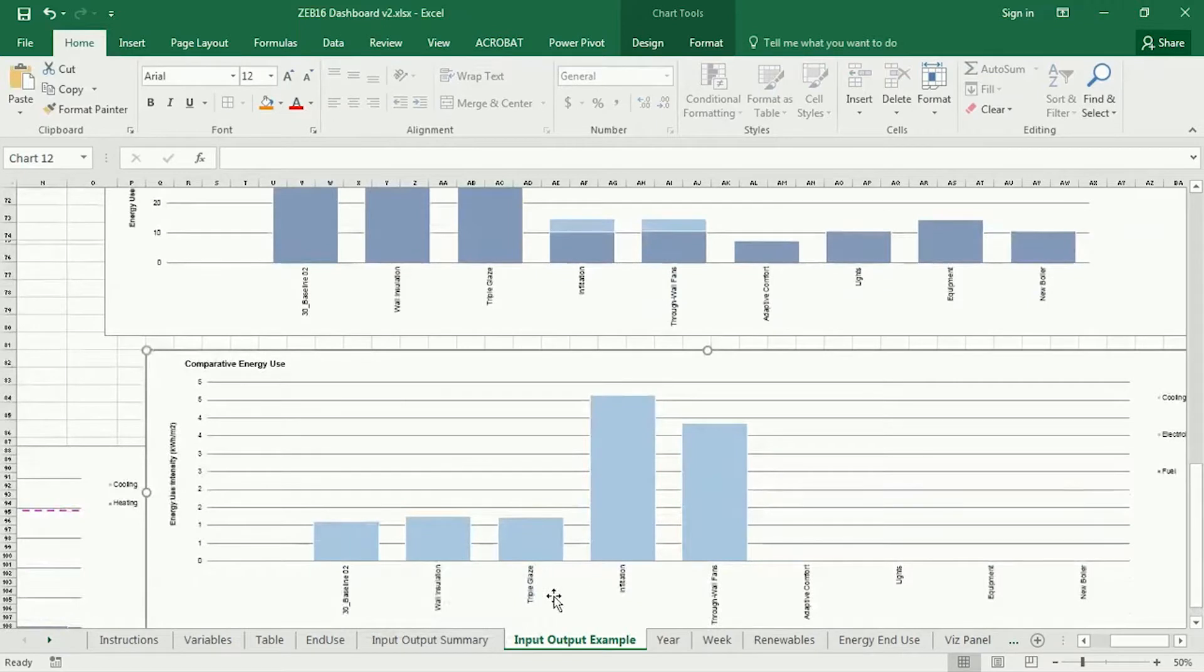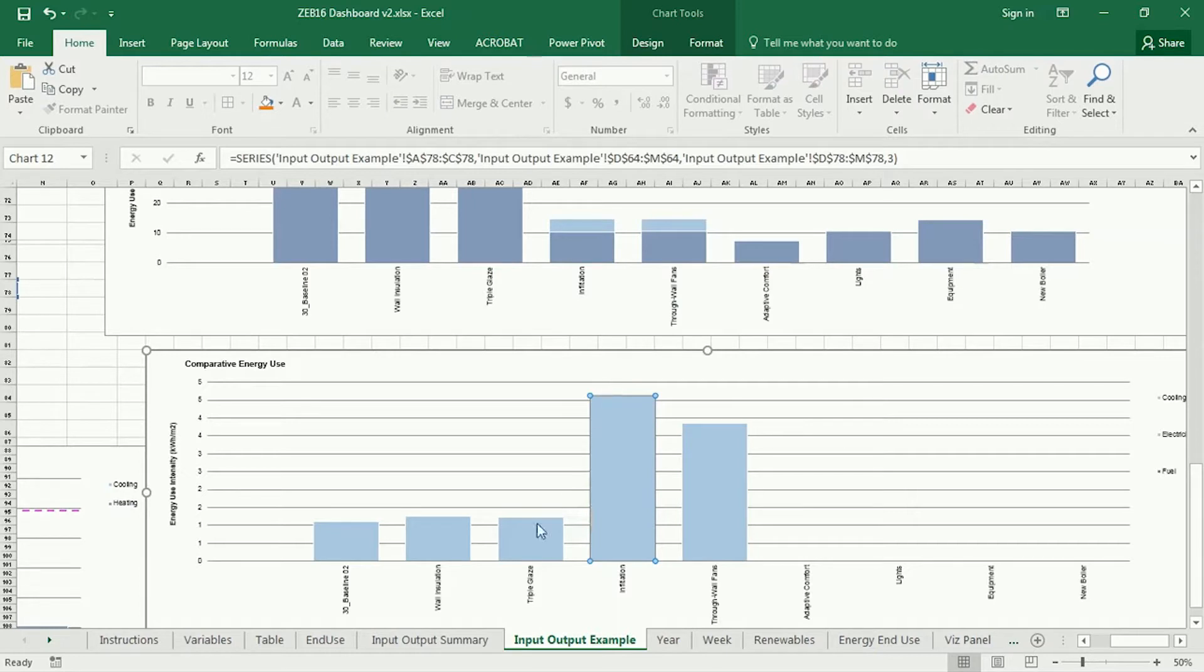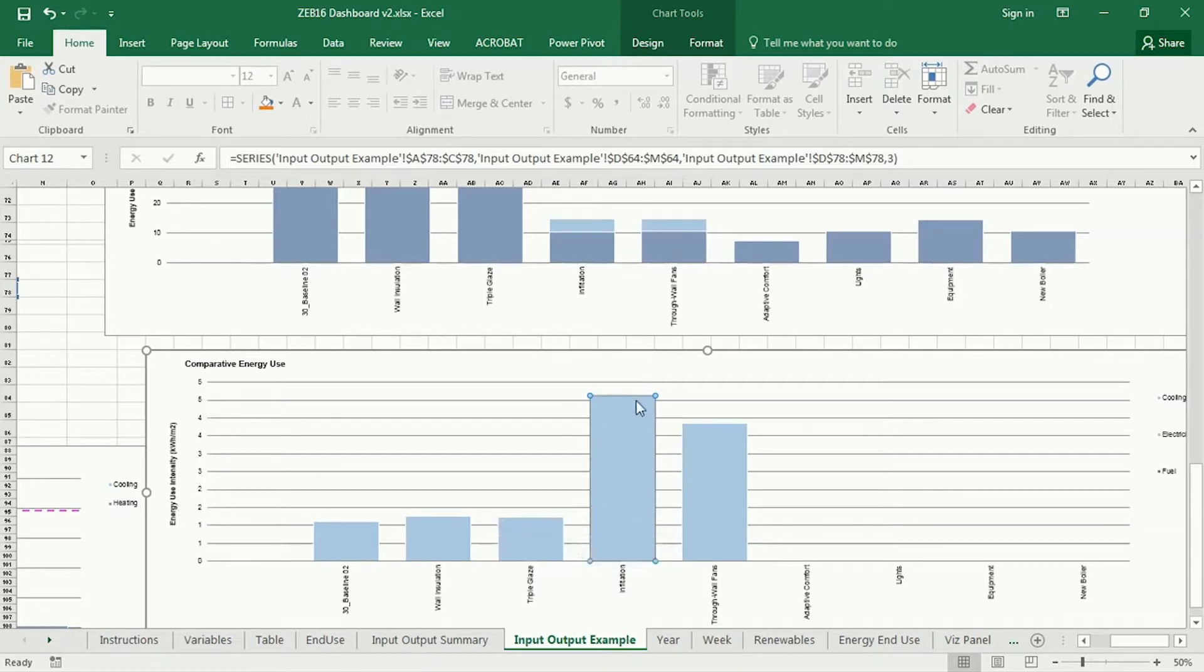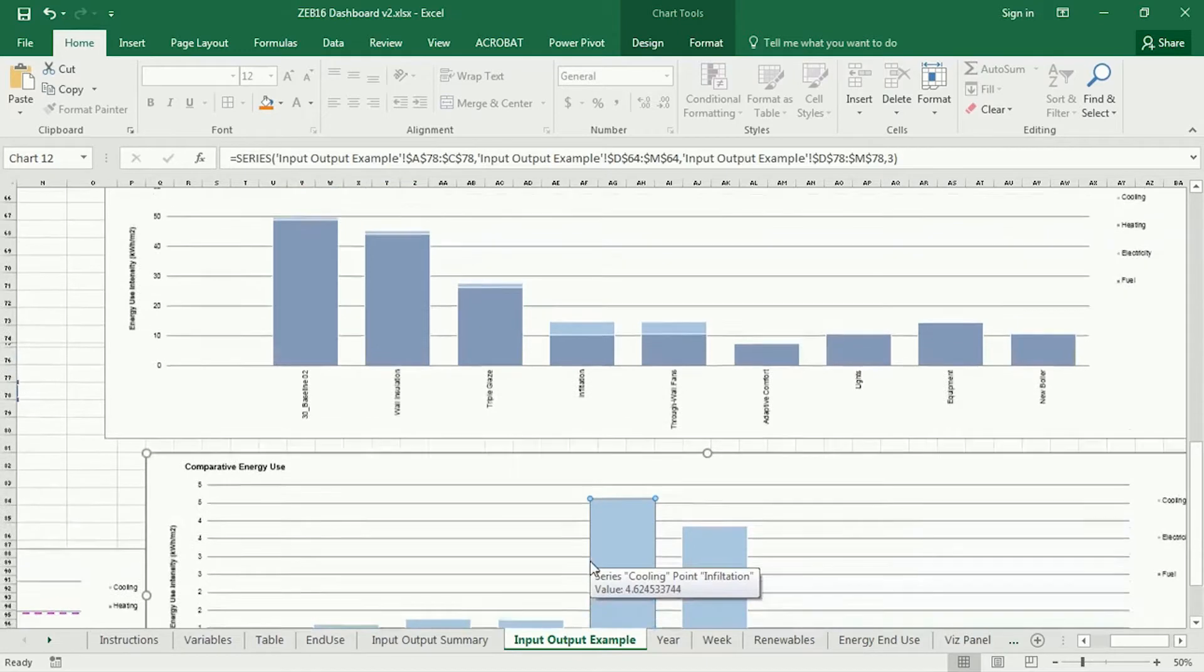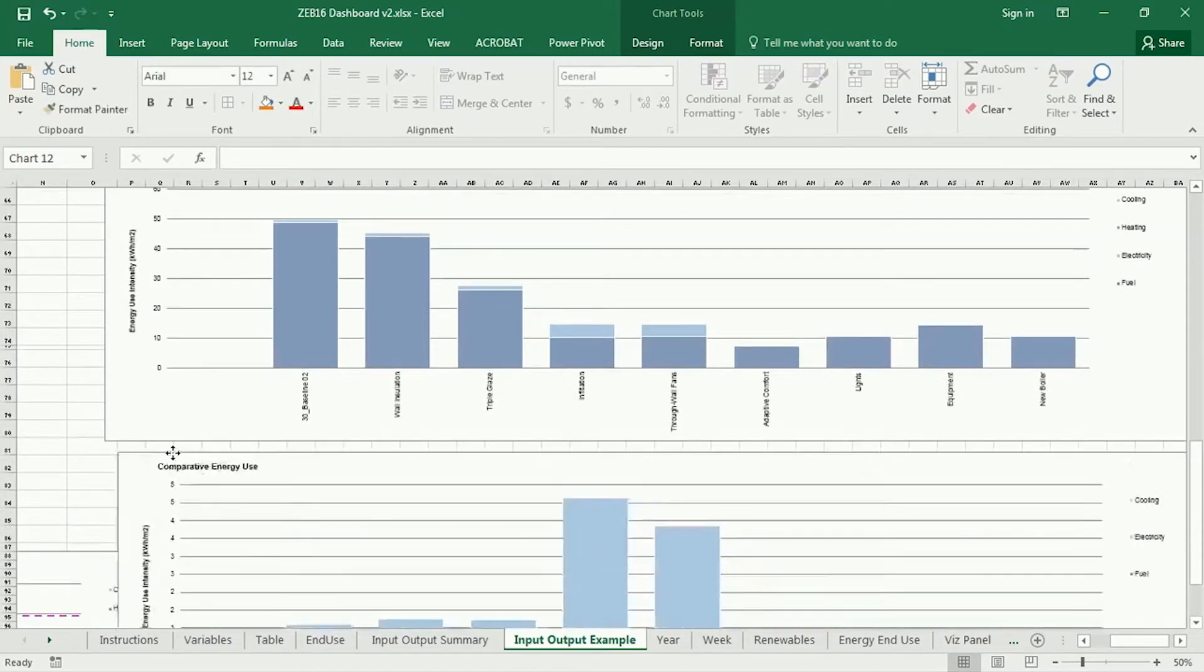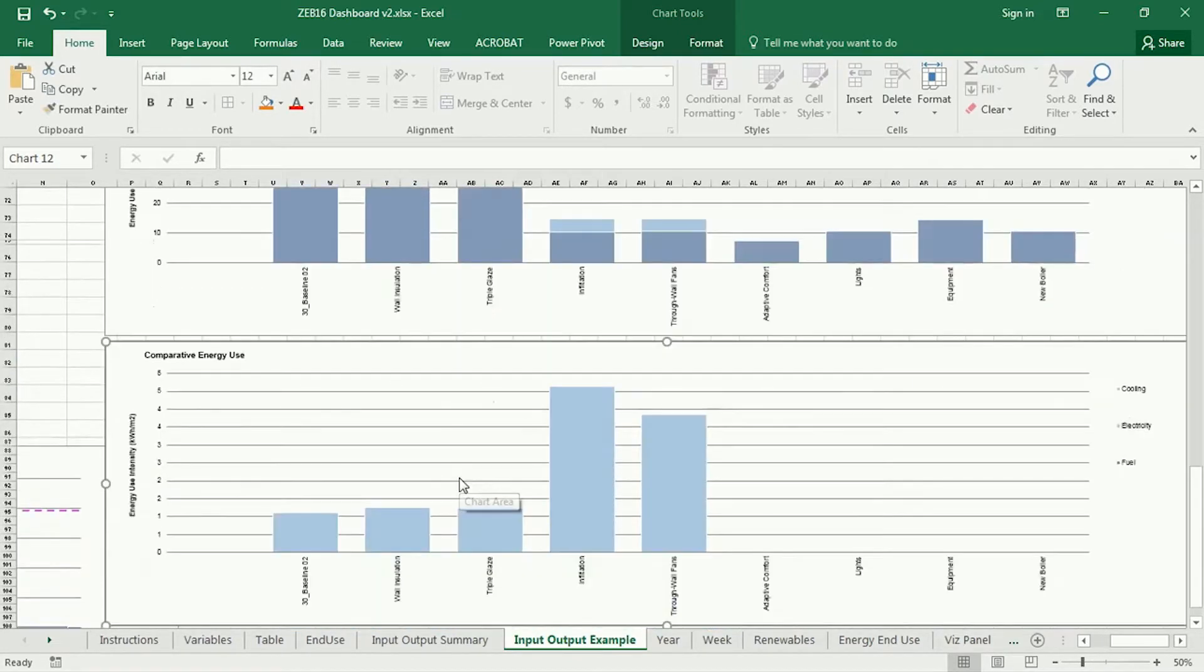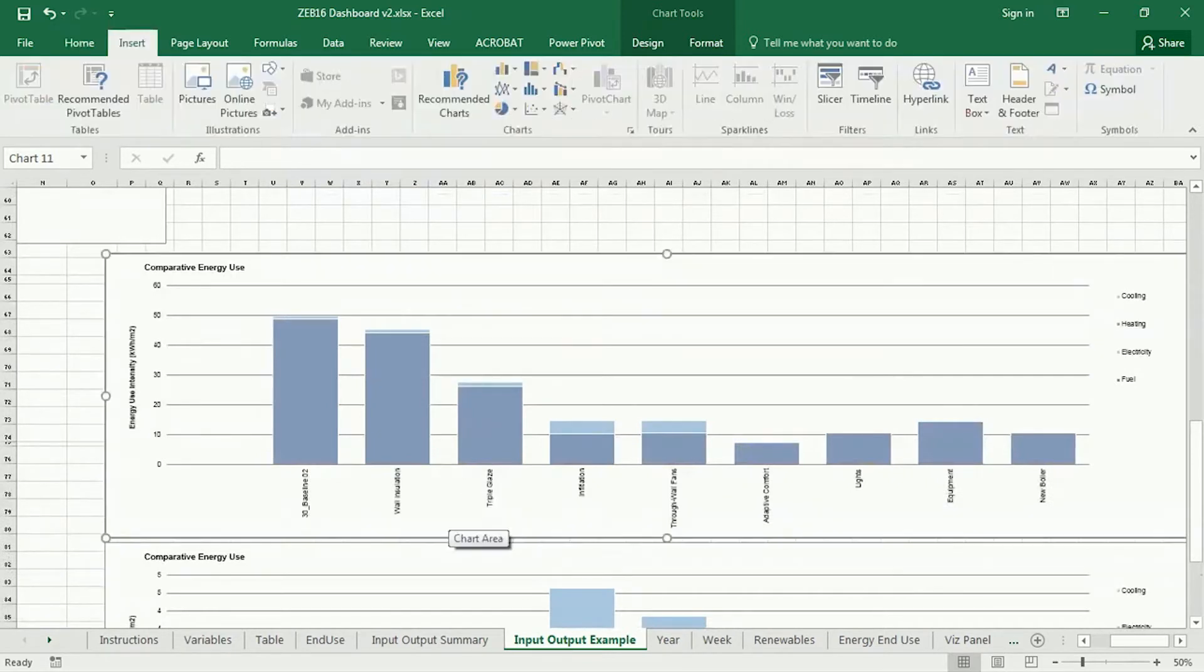And as a result of it being heating dominated, I can't really see so much what's the cooling impact. So I could further copy that and paste it and then delete the heating. And then I would see a lot better what impact things have on the cooling. So, for instance, this move from triple glaze to infiltration dramatically increased the amount of cooling, but it's actually not, it's relative to itself. It's not a large number in any case. So that could be a useful tool to analyze the impacts of the different measures.